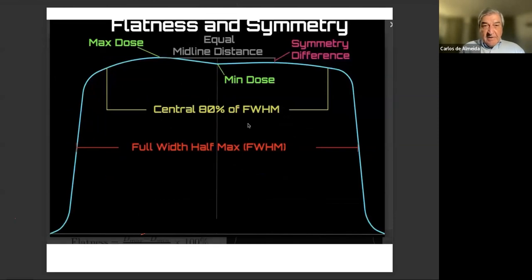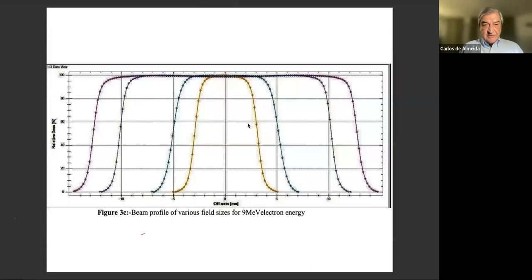Now, also the measurement of the beam flatness, you must have a detector with a resolution good enough to see what is happening here at the penumbra area, and also in this midpoint. This is even more important now that we have flattening filter-free beams, where the distribution is done in a slightly different way. Next one. For electrons, the same: you must have a detector that could see small differences in this gradient region, which is very, very steep, but you must know that.